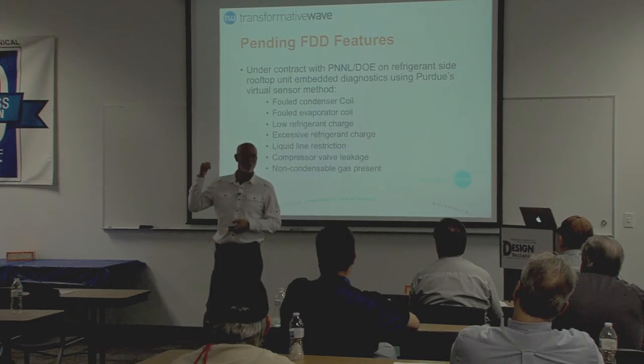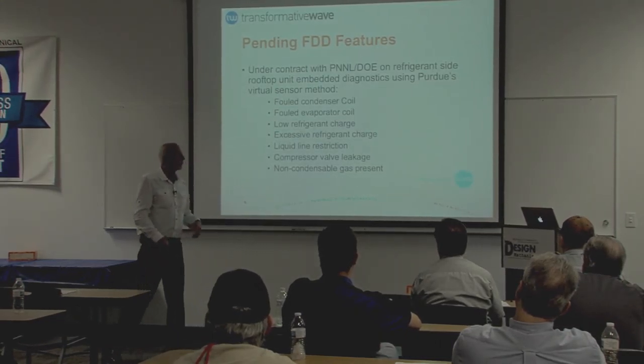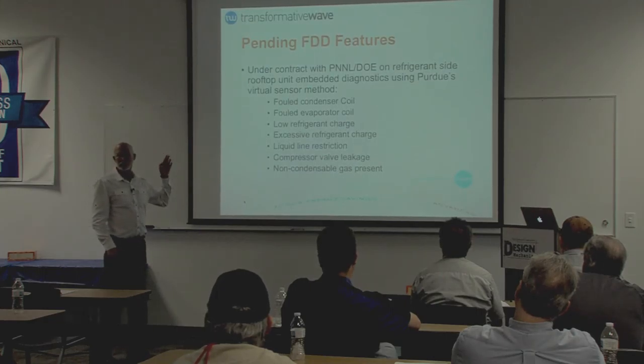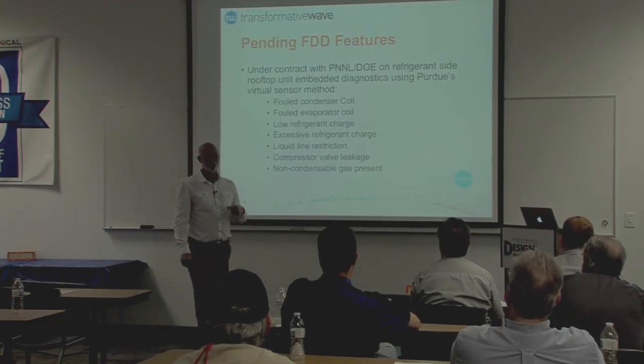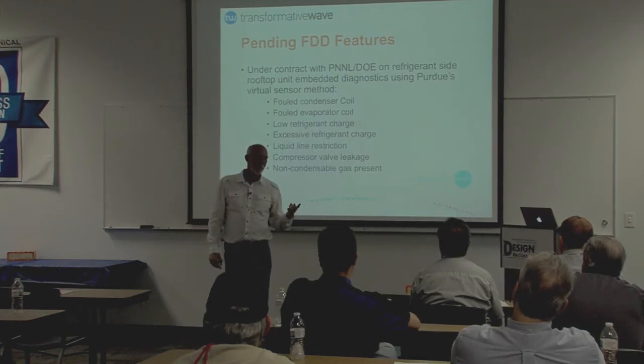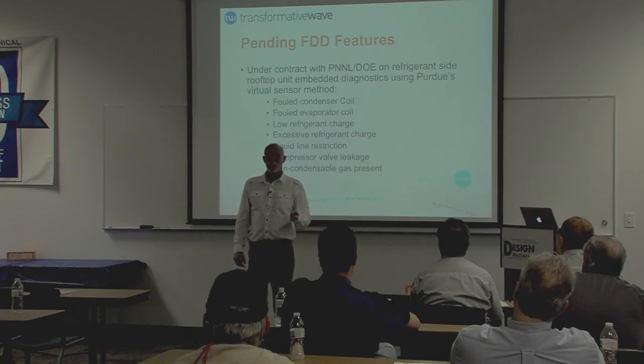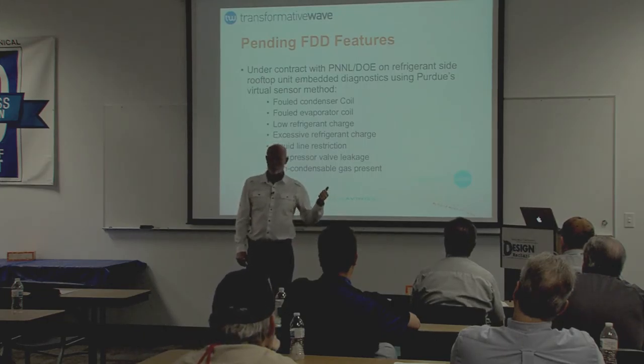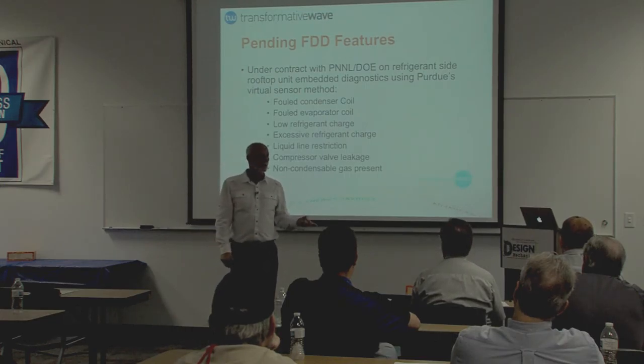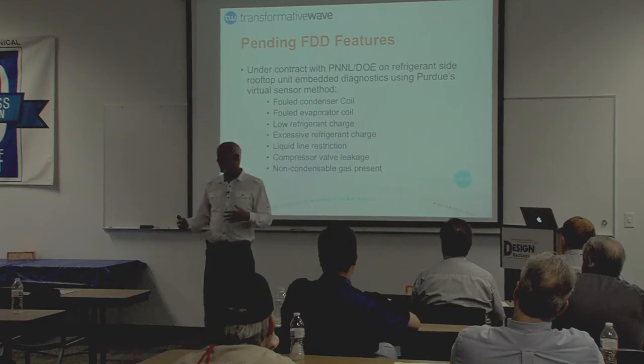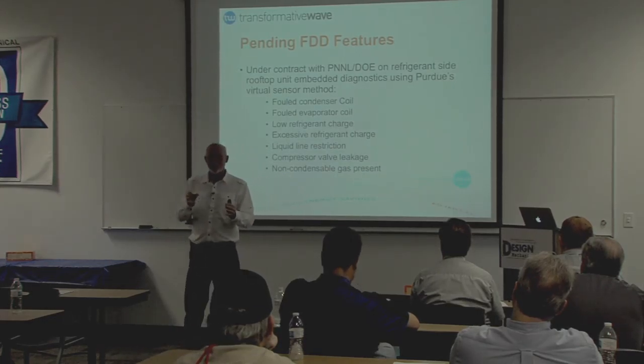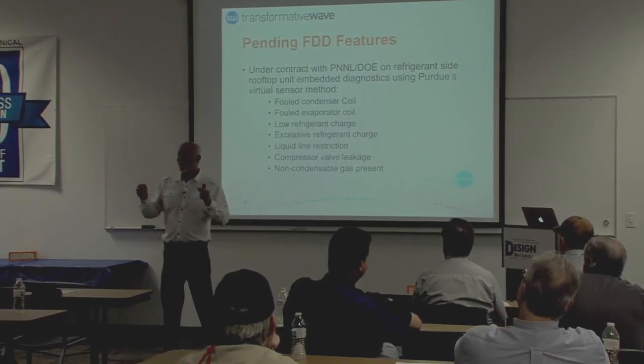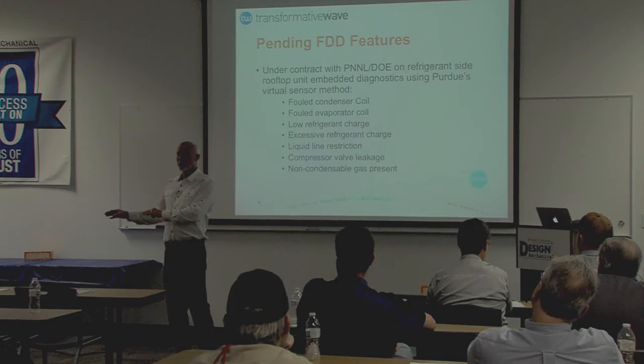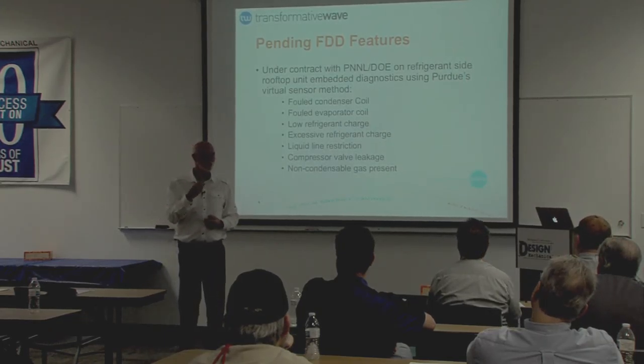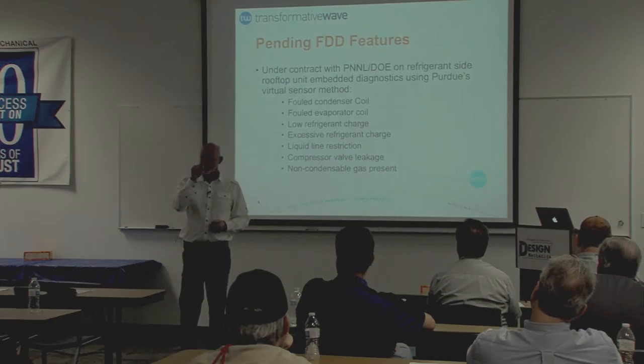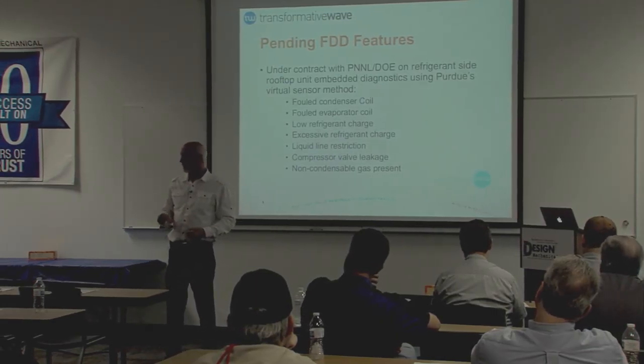So this suits us very nicely. Basically, it's four temperature sensors, and we can tell you if you have a dirty condenser, a dirty evaporator, a low charge or undercharge, an overcharge, non-condensables in the refrigerant - so if you get air in the system - a clogged metering device or obstruction in your metering device, or bad valves. All these seven different faults on the refrigeration cycle can be determined with four temperature sensors strategically located on certain parts of the refrigeration system.